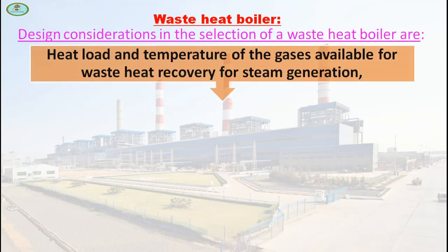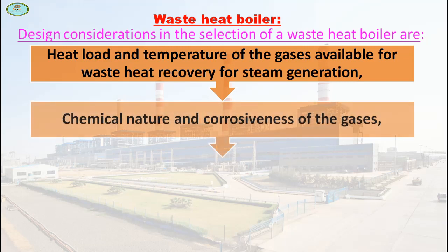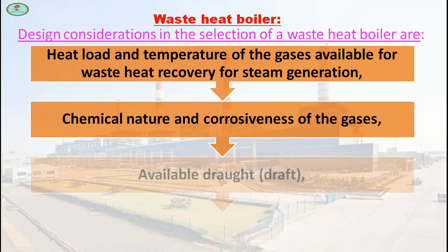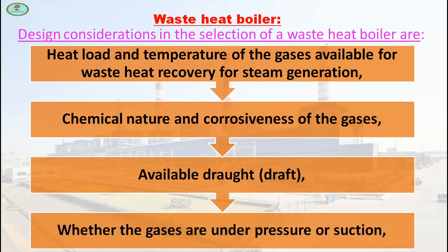Design considerations in the selection of a waste heat boiler are as follows. Heat load and temperature of the gases available for waste heat recovery for steam generation. Chemical nature and corrosiveness of gases. Available draft. Whether the gases are under pressure or suction.